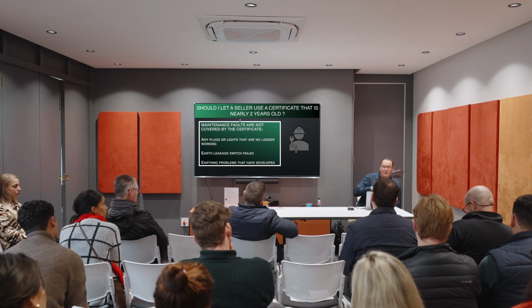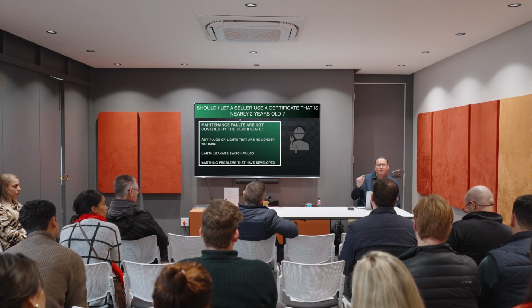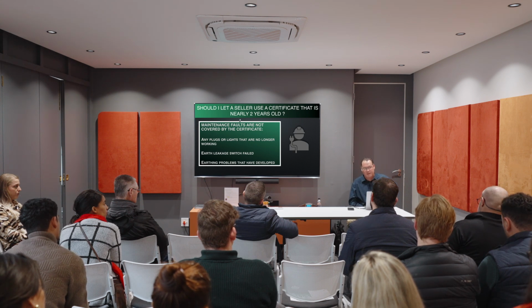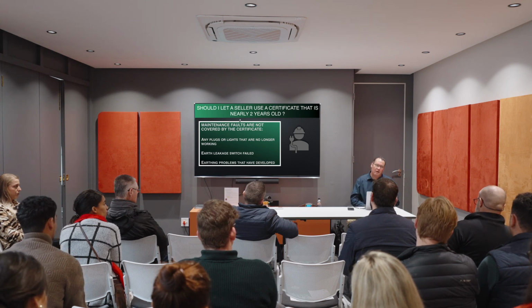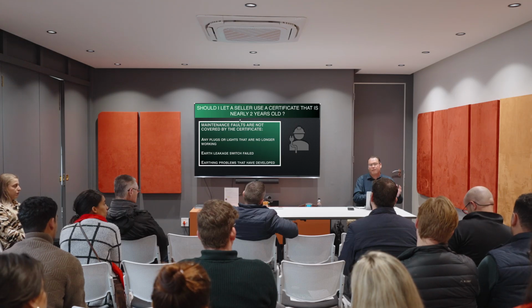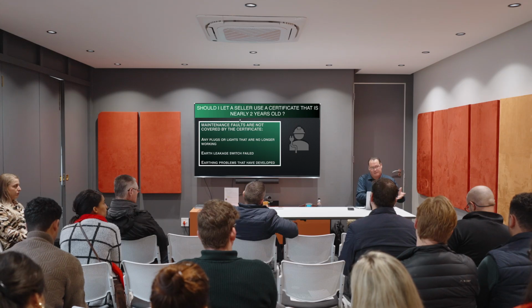They didn't say, and we went to check it, everything was earthed properly. There just wasn't an earth wire, and so they're quoting for it. This has happened in Harfield Village, Claremont, Gardens, and we've seen it in North Pine. You won't find it in a newer area because they don't have metal conduit, they use plastic.